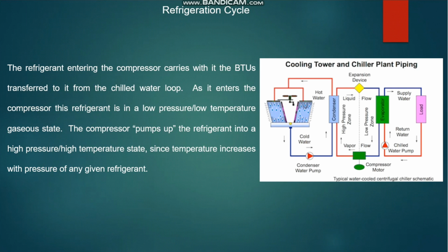Here we need to understand the concept of the refrigeration cycle first. The refrigerant entering the compressor carries the building load, that means the chilled water return temperature at this point. At this level we can separate the chiller into two sides: one is the high pressure zone, one is the low pressure zone. The refrigerant entering the compressor carries the building BTU or building load. When it enters the compressor, the refrigerant is at low pressure and low temperature. It is in the gaseous state, not in the liquid state.